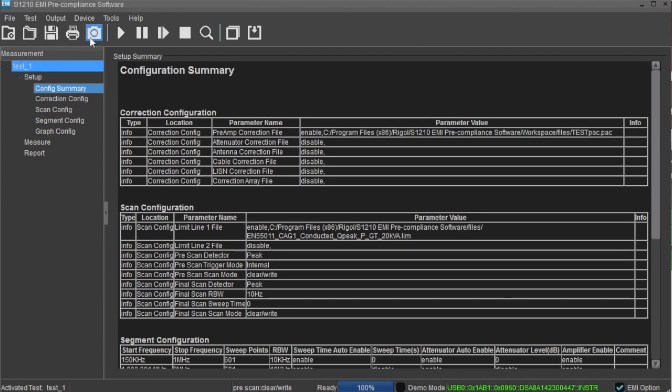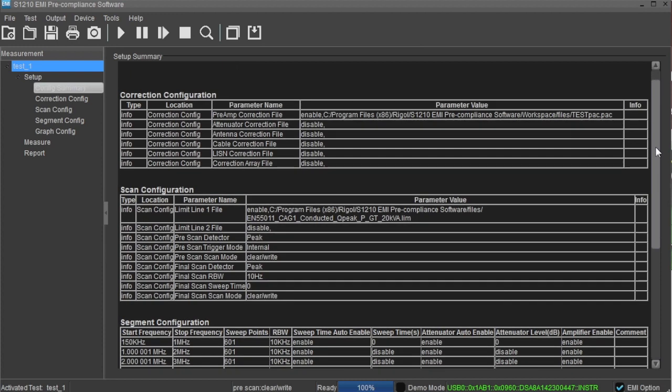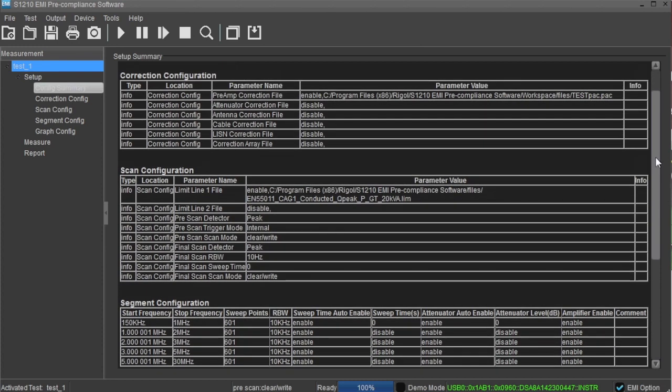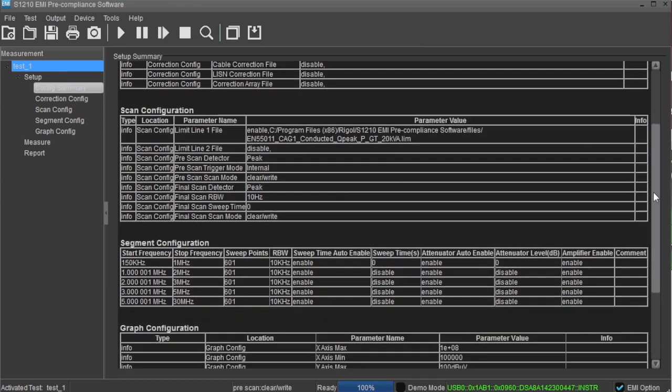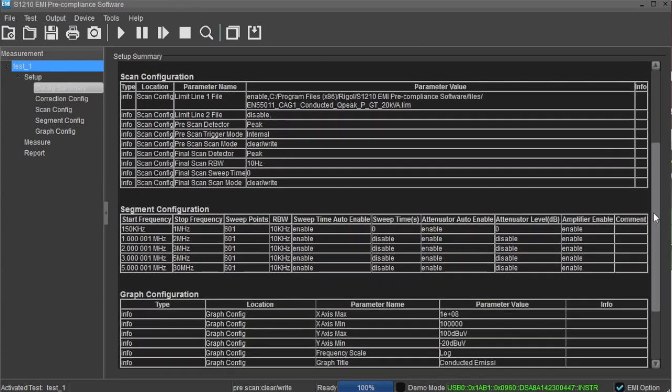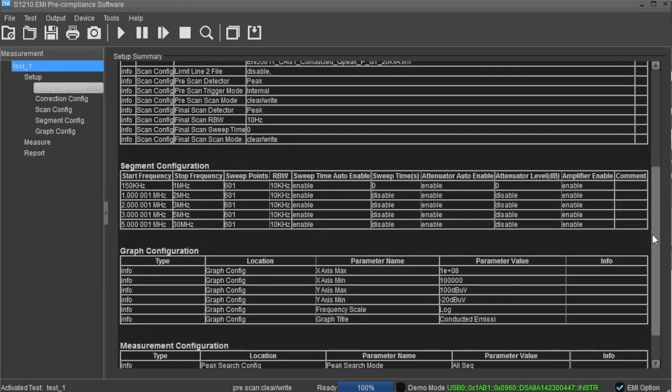On the left side of the window there are a number of labels that help to configure the scan and also monitor the performance of your system. The configuration summary shows all of the instrument settings, environmental, and other setup parameters that may be important to your final pre-compliance report.